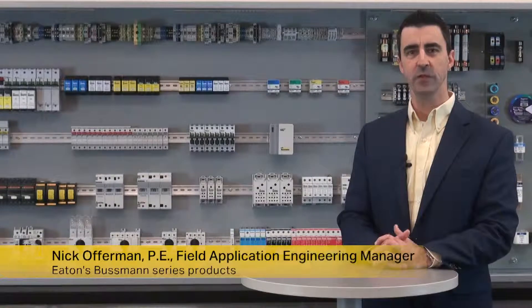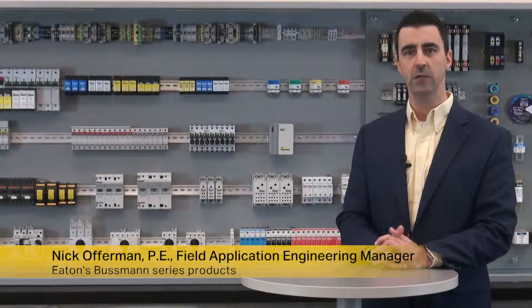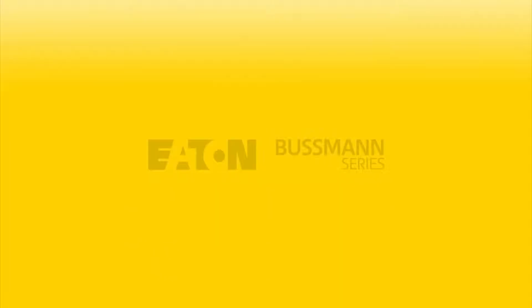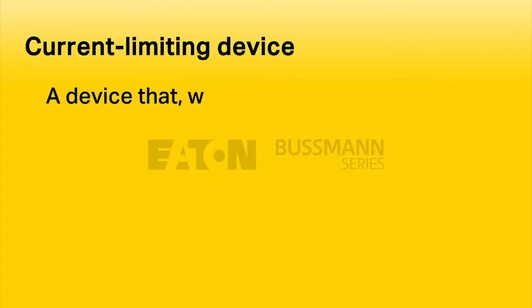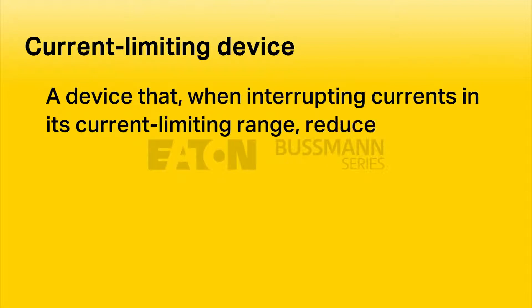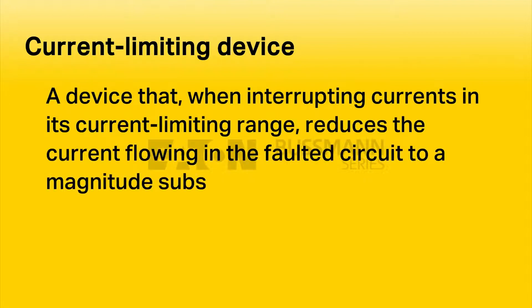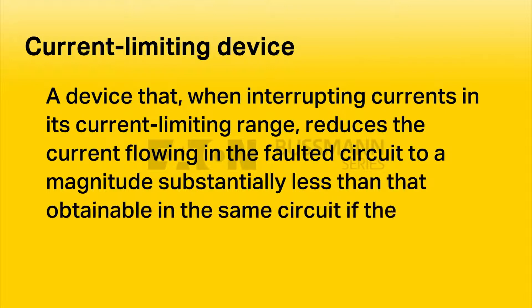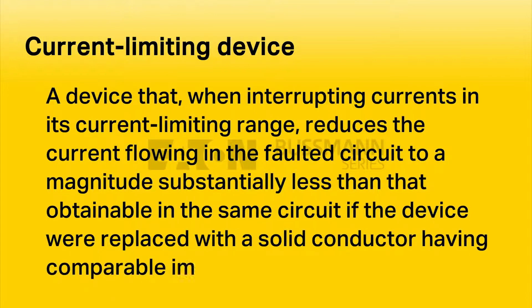Current limitation is a function of how quickly the fuse can react to a fault and clear it before the fault current can build up to destructive levels. NEC 240.2 defines a current limiting device as a device that, when interrupting currents in its current limiting range, reduces the current flowing in the faulted circuit to a magnitude substantially less than that obtainable in the same circuit if the device were replaced with a solid conductor having comparable impedance.